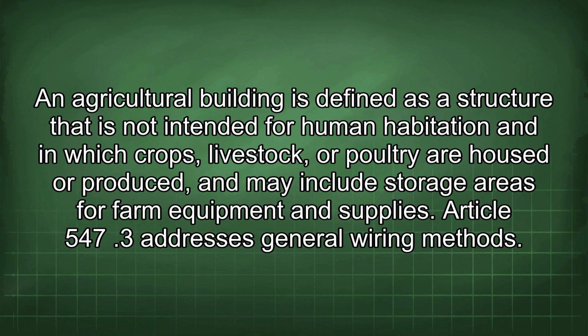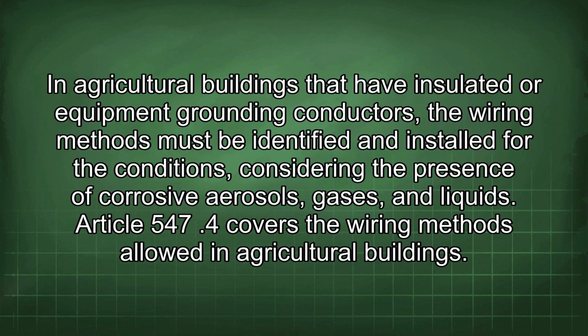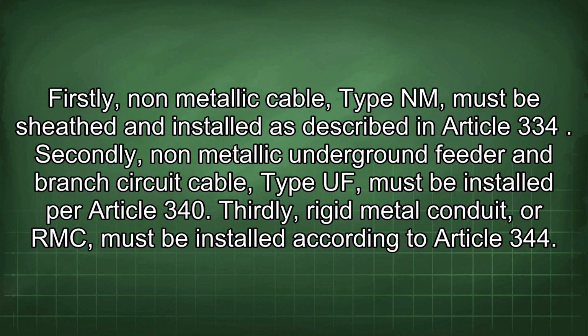Article 547(3) addresses general wiring methods. In agricultural buildings that have insulated or equipment grounding conductors, the wiring methods must be identified and installed for the conditions, considering the presence of corrosive aerosols, gases, and liquids. Article 547(4) covers the wiring methods allowed in agricultural buildings. Firstly, non-metallic cable, type NM, must be sheathed and installed as described in Article 334. Secondly, non-metallic underground feeder and branch circuit cable, type UF, must be installed per Article 340.